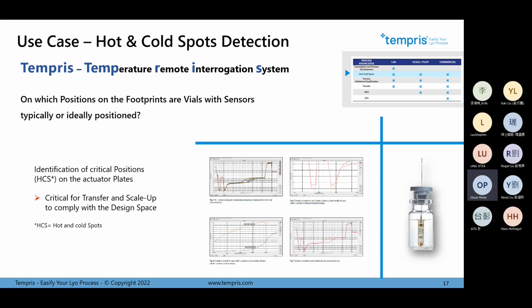We also have the loading door, what we call the pizza door, the loading door for automatic systems, which does not have the same insulation material. Then there is how the silicone oil comes to the shelves, and whether there is a manifold inside or outside of the freeze dryer, inlet and outlet. We consider all these phenomena for every specific freeze dryer, and we recommend some measurement points from the beginning. Then it's not really necessary to do the 5-star pattern, five sensors per shelf, typical for measuring in all the shelves.